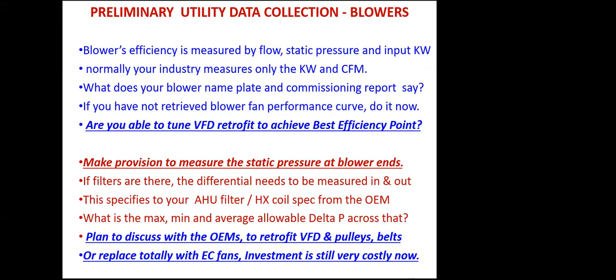If you are going for a V belt, you can go for a cogged belt, and that also gives an excellent savings. But you have to make provision to measure the static pressure. The static pressure gradient from the blower to the machine, it may be 10 or 20 meters distance, but the point is how much duct loss is happening. This is also a point of measurement, and whatever static Pascal drop is happening, that is a point to be immediately attended to.